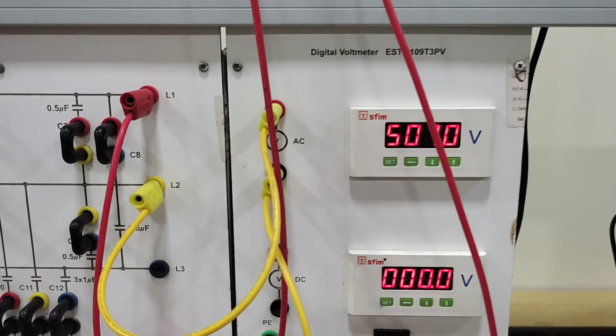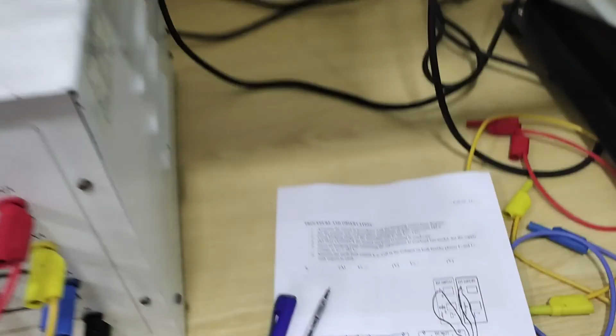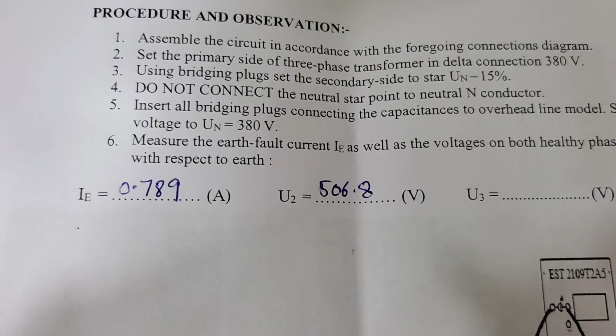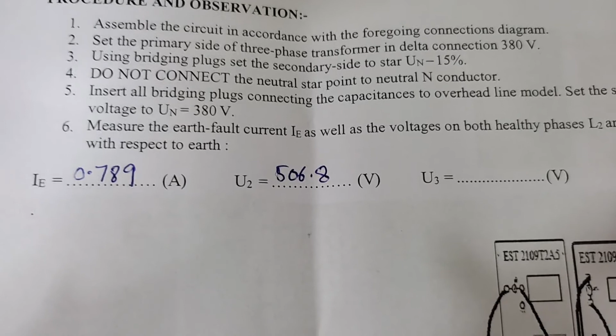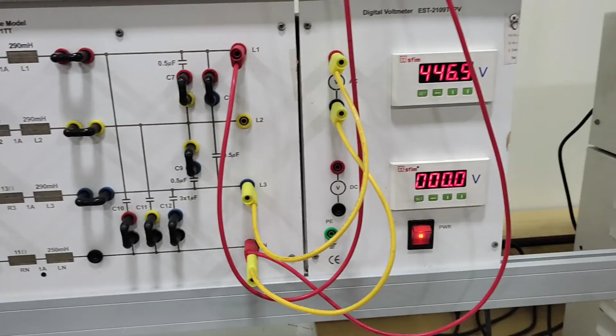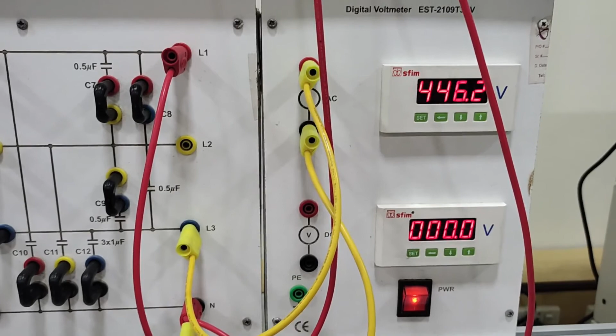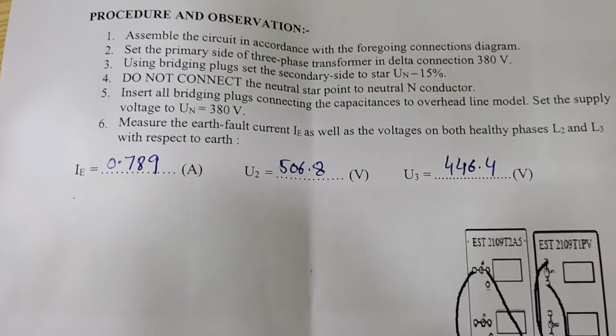So in order to measure the voltage for the third phase, what we have to do, first we will note down the readings, and then we will check the voltage for the third phase. So students, we will note down the readings here. Students, you can see here that we have noted down our short circuit current and voltage of the second phase. Next we have to measure the voltage for the third phase. For that we will connect the voltmeter towards the third phase. So students, here now I have connected the voltmeter in parallel with the third phase, and you can see that short circuit current remains same, but we will measure the voltage for the phase L3, that was 446.3, and we will write it on our manual. So students, here we have noted down the readings.